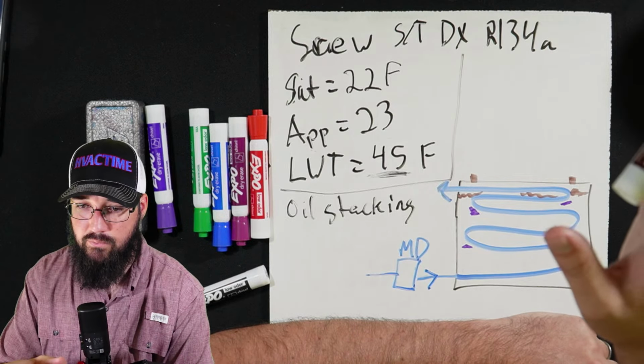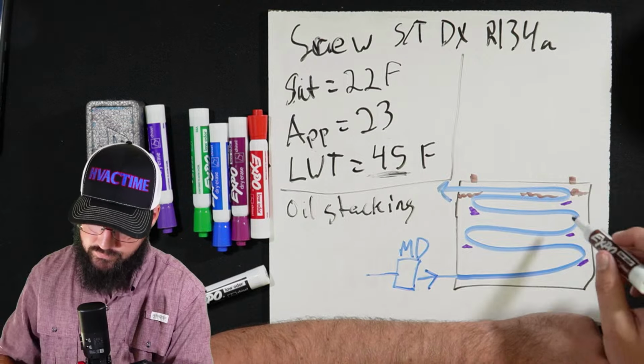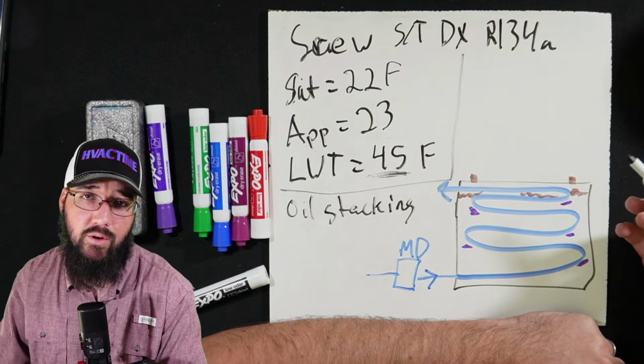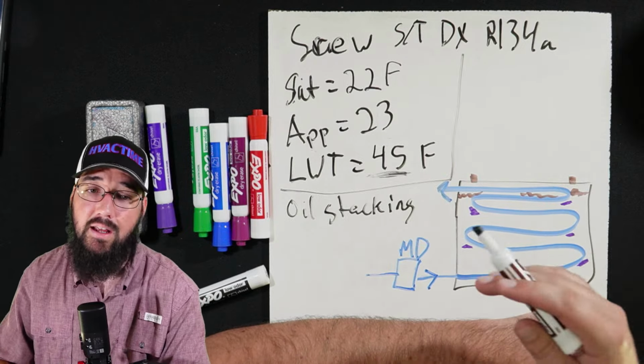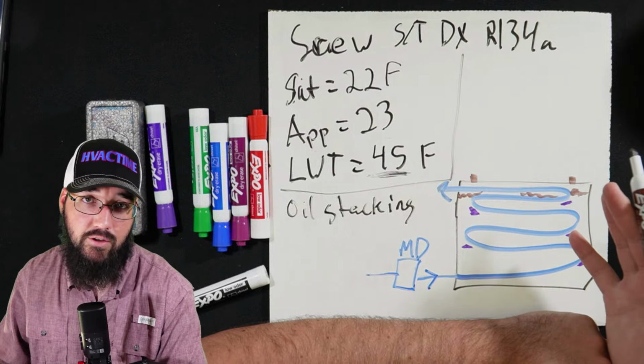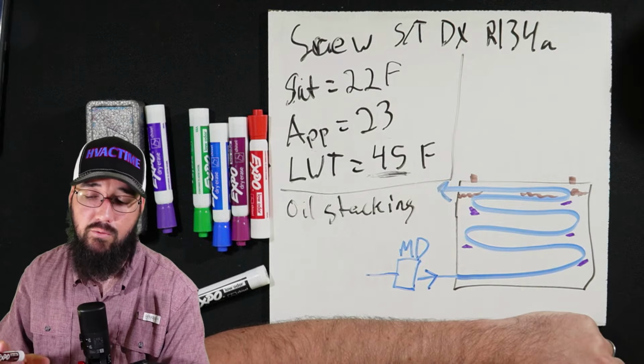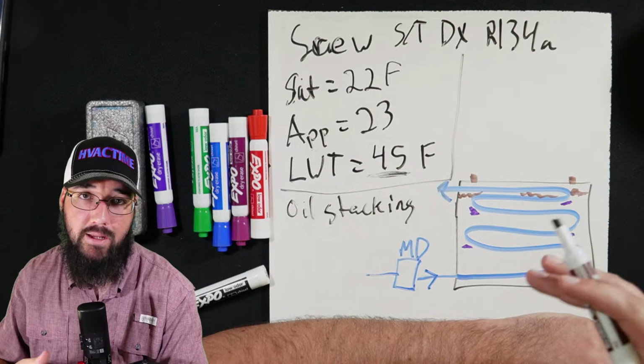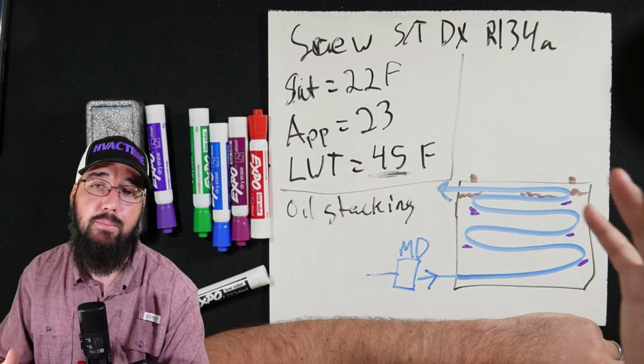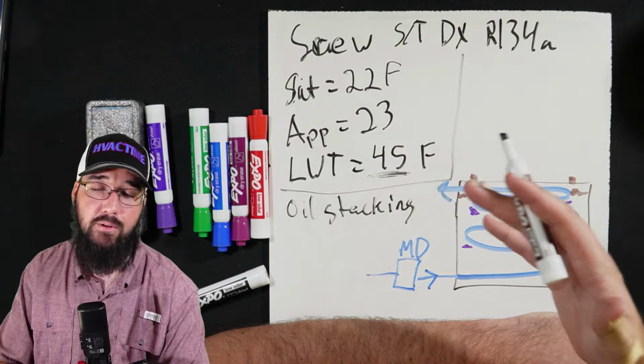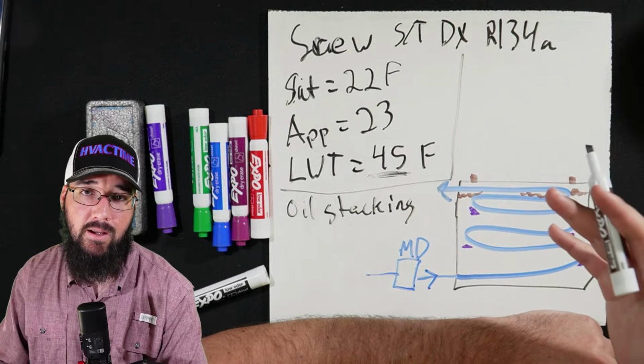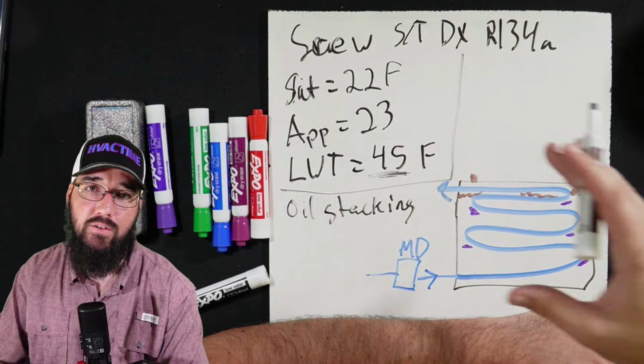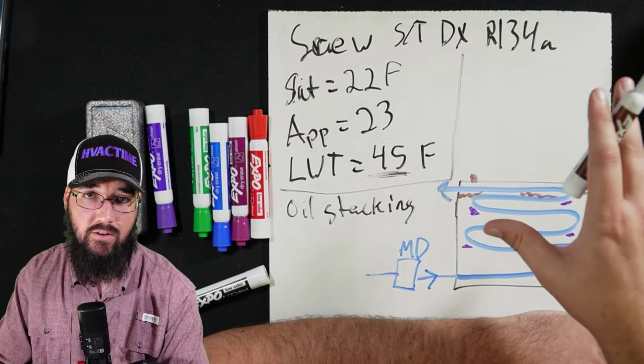And to Sanchez's point, depending on where that evaporator is in the circuit, it may only affect one of the chillers. Okay, so this air trapping could be isolated to one specific machine depending on where it is at on the header assembly and how it's all piped in. All that plays a difference into where does that air go and how does it get stuck there.